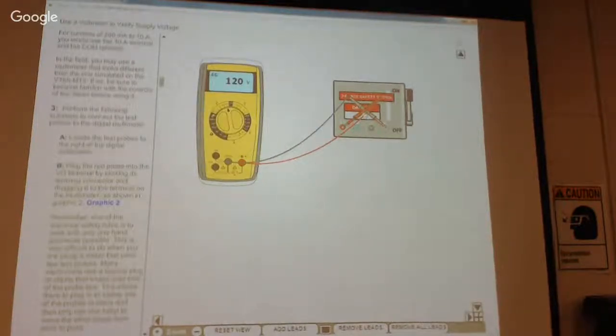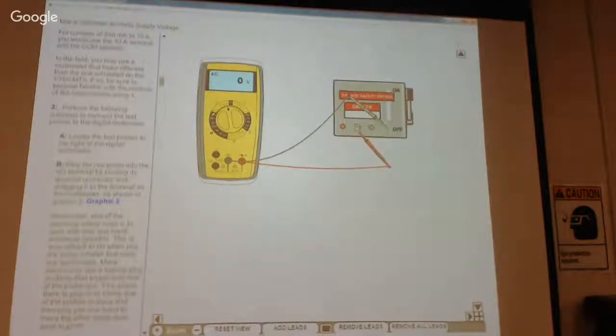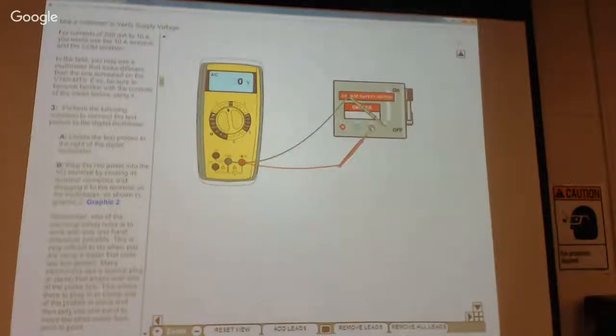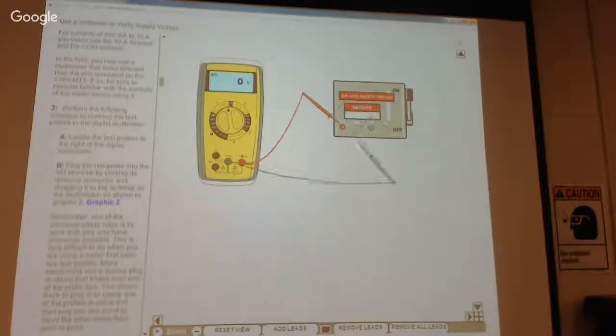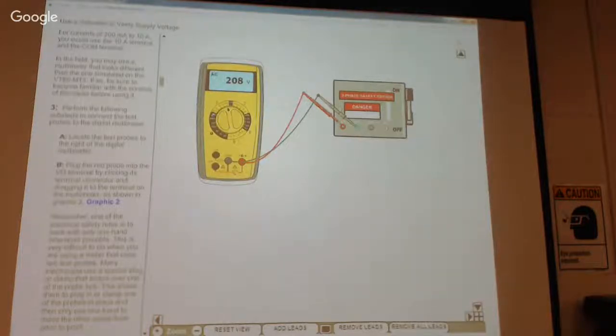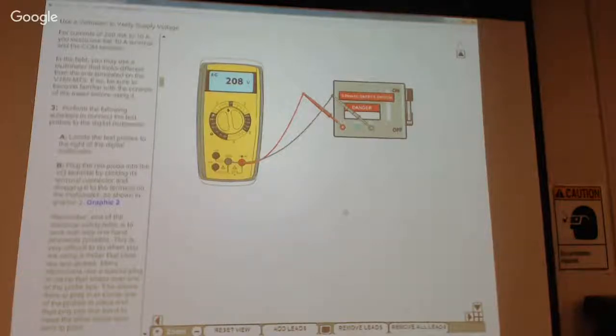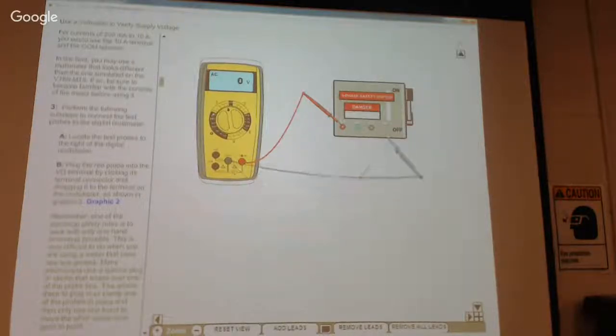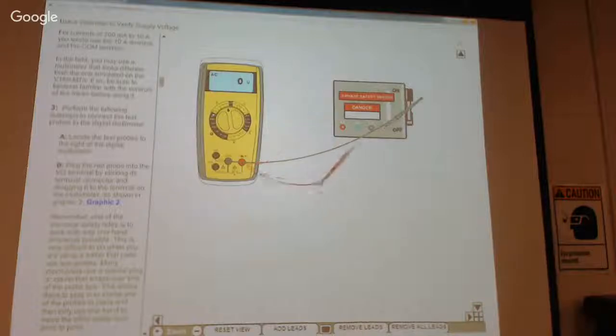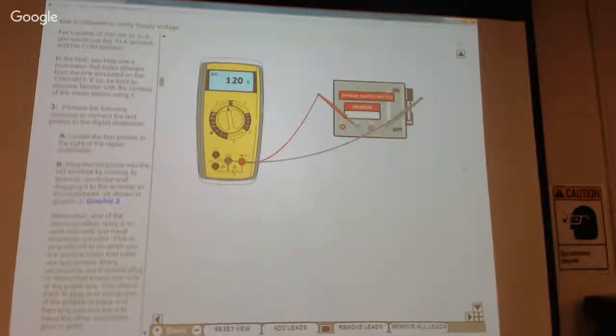We have 120 volts. Here we have 120 volts. Here we have 120 volts. That tells me that I have all three legs of this circuit. This is 220. This is what we have in the classroom. If I check between them, I should read 200, well, 208. You'll notice when people talk about 220 or 208, they kind of just run them together. They don't distinguish too much. All right, so we've done that.